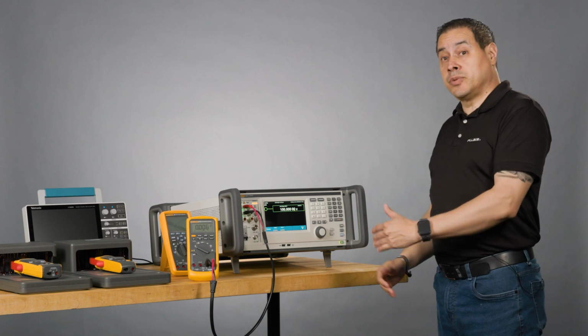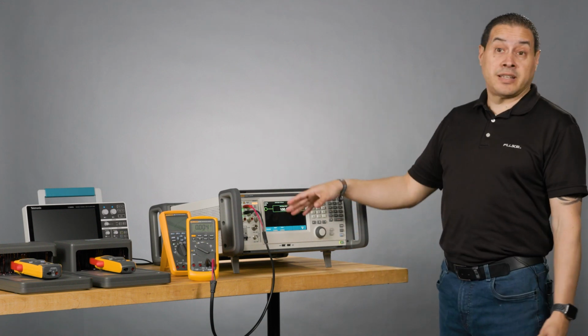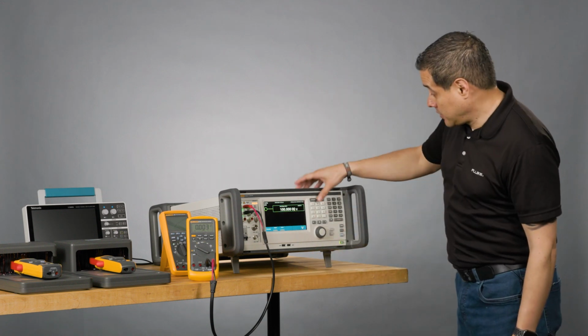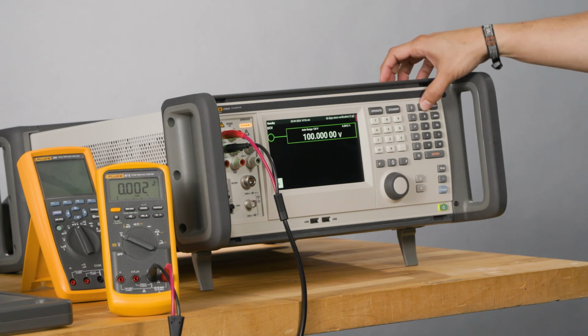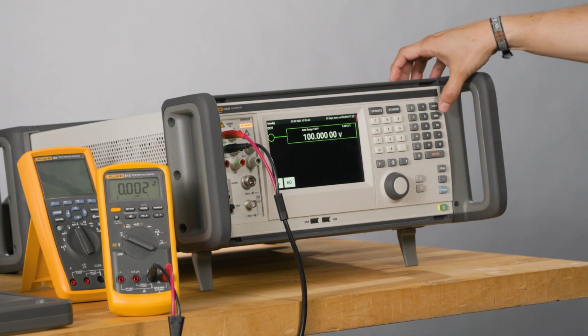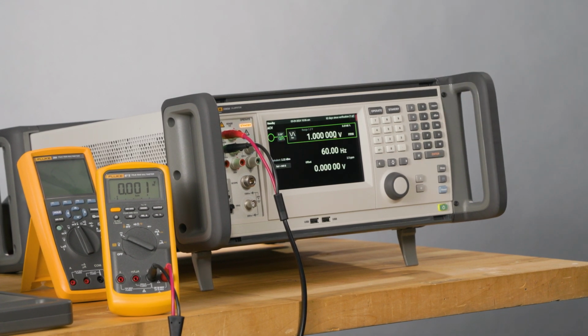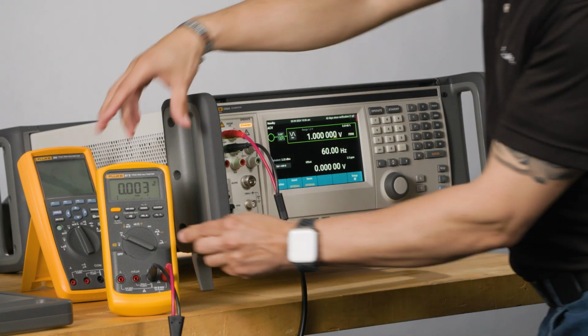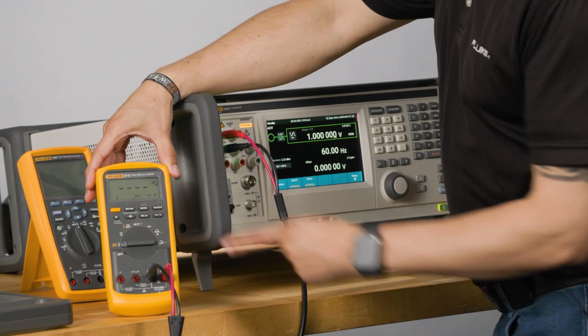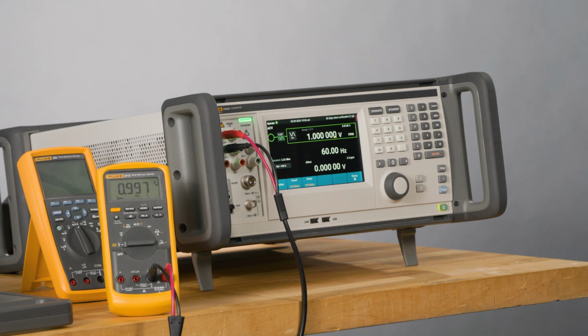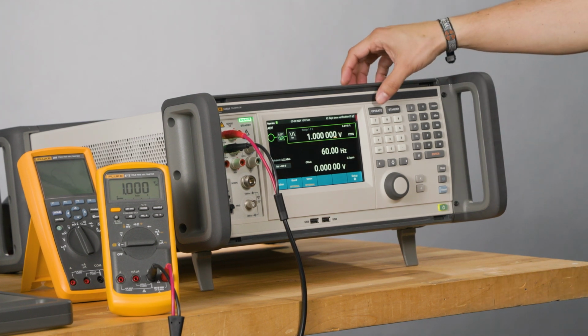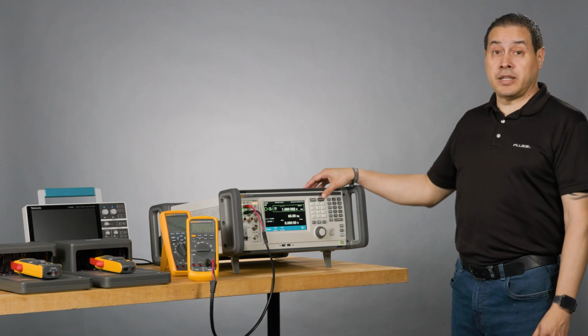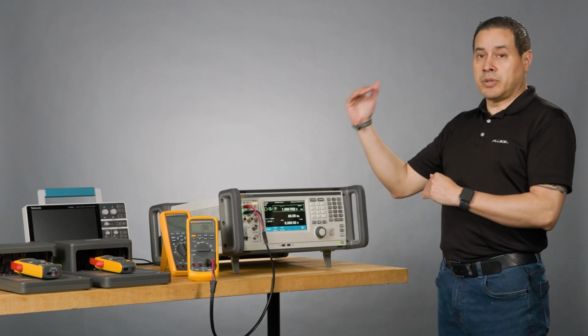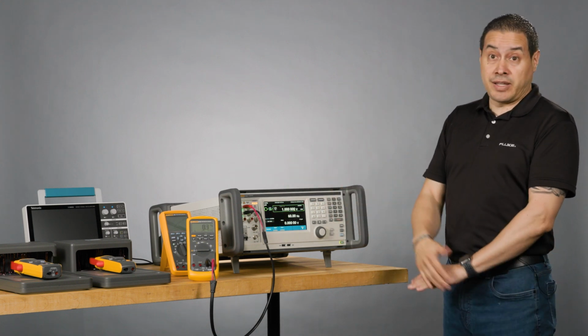And then I'll be done with DCV. Now I'm going to jump to ACV. In this case, I don't need to change the cables. So 1 volt, 60 hertz, enter. And then I need to change my knob to ACV. I got 1. You need to wait to stabilize. And then the same process that I did in DCV, jump to the calibration point that the manufacturer indicates.